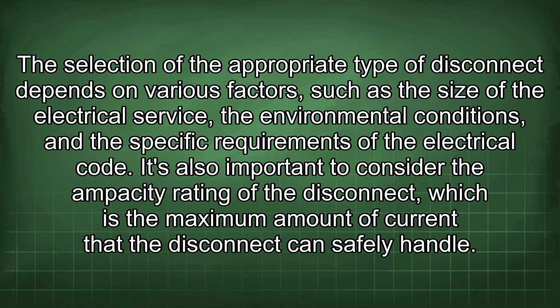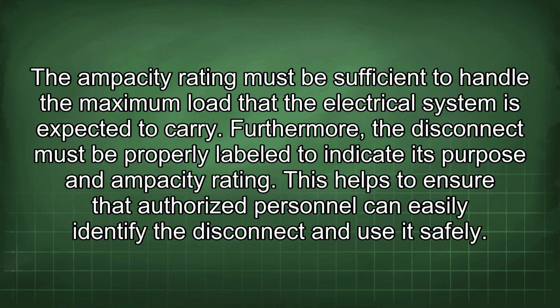The selection of the appropriate type of disconnect depends on various factors such as the size of the electrical service, the environmental conditions, and the specific requirements of the electrical code. It's also important to consider the ampacity rating of the disconnect, which is the maximum amount of current that the disconnect can safely handle. The ampacity rating must be sufficient to handle the maximum load that the electrical system is expected to carry. Furthermore, the disconnect must be properly labeled to indicate its purpose and ampacity rating. This helps to ensure that authorized personnel can easily identify the disconnect and use it safely.